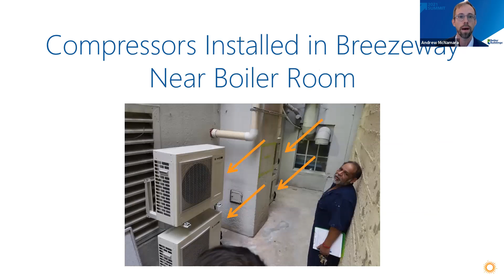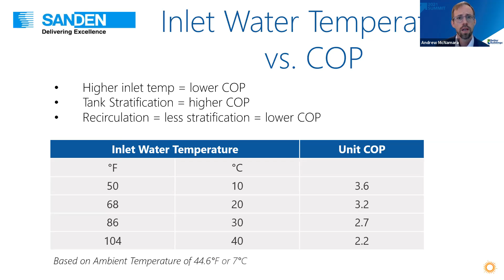Then on the next slide, you can see a key design consideration. COP is the operating efficiency, or the coefficient of performance. If the COP drops below about 3.6 in PG&E territory, the heat pump water heater will actually cost more to operate than the boiler it replaced. One of the keys to achieving the target COP is managing the inlet water temperature. If your property has problems with crossover flow or other distribution issues, the inlet temperature to the heat pump water heater can rise if it isn't properly managed, and the efficiency can plummet, which increases your operating costs. This was a key lesson learned from our early installations: managing that in existing properties.